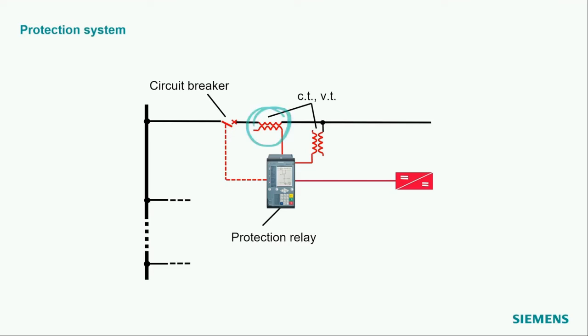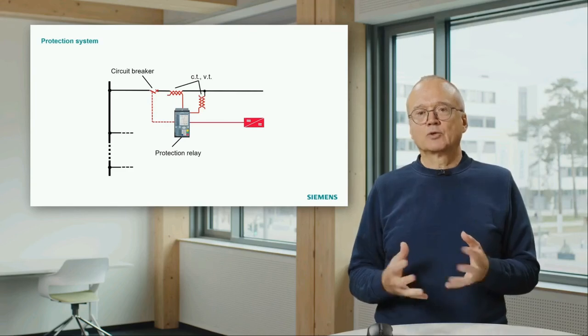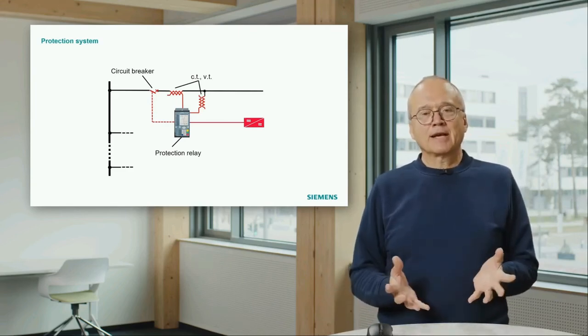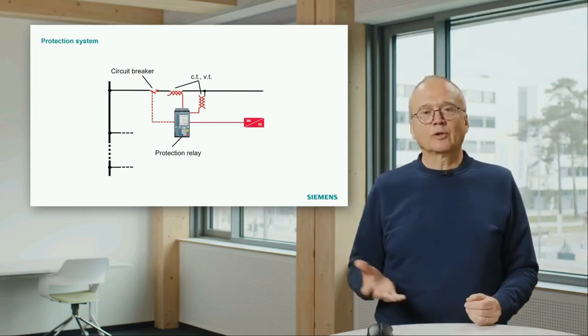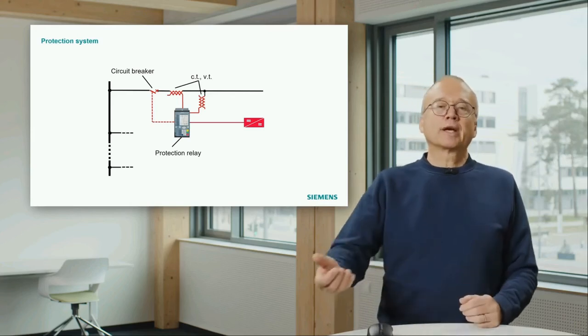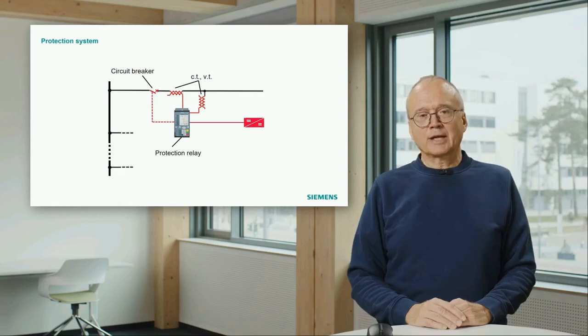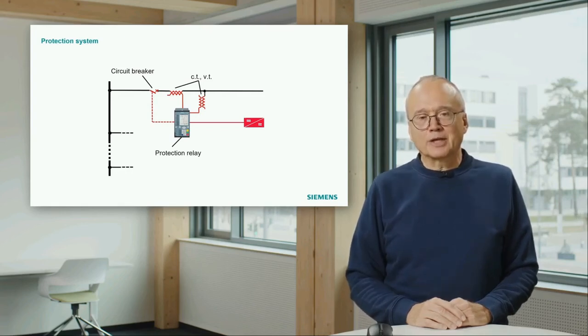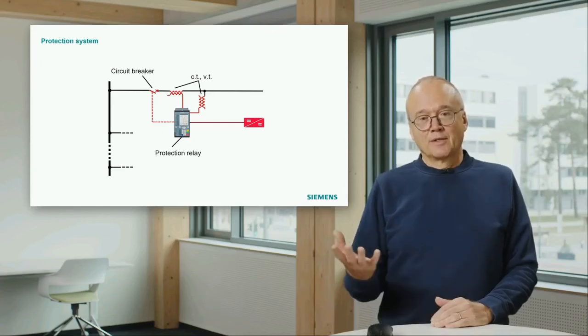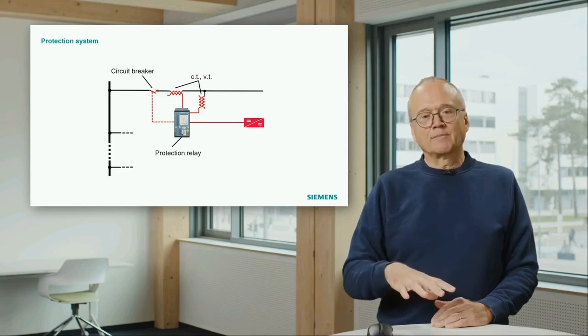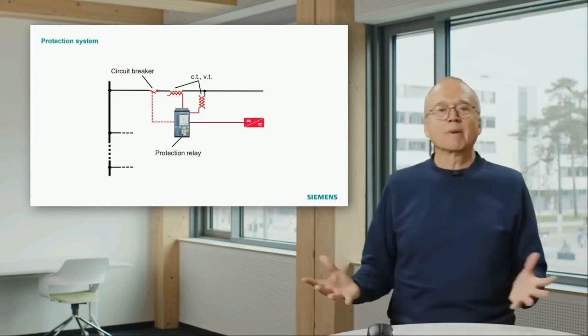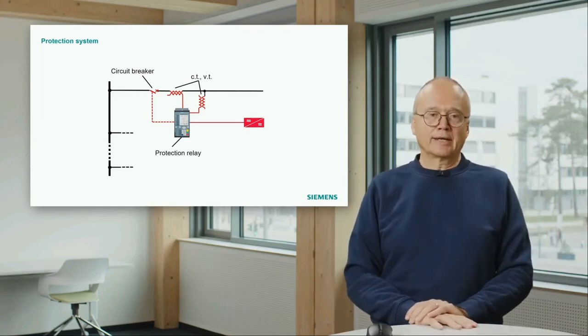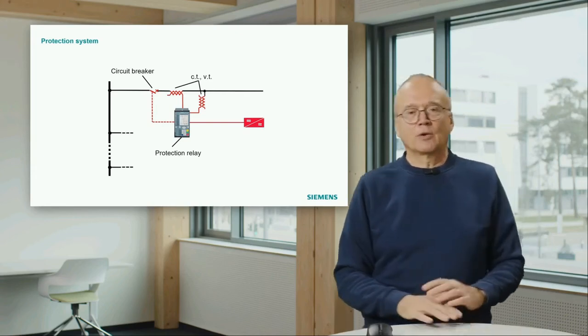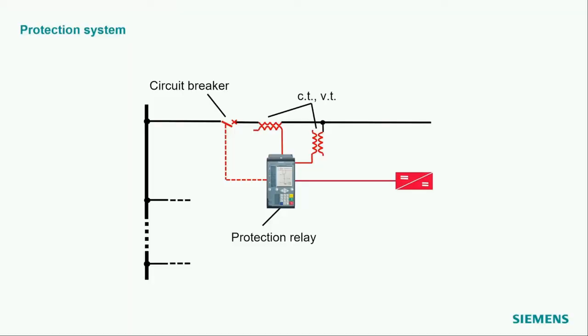Then we see current transformers and voltage transformers here. Why do we need that? The protection relay has to measure currents and voltages on the line to decide whether there is a short circuit or not. But as the line may have 20 kV, 132 kV, 400 kV or whatever, we cannot connect the line directly to the protection relay. We connect it via the so-called instrument transformers. That means the voltage is transformed down to a reasonable level, and also the big current which may flow, we may have 10, 20 kiloamps in case of a short circuit, is transformed down to a level which the protection relay can use.